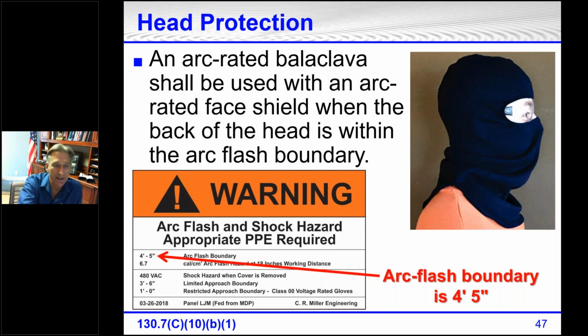All right, so with this label, this is a label that I drew up, and you may not be familiar with some of my drawings and illustrations and some of the books that I've written and published. The arc flash boundary on my label is 4 feet 5 inches. Do you think the back of your head is going to be within the arc flash boundary, being that it's 4 feet 5 inches? Well, yes, of course it is.